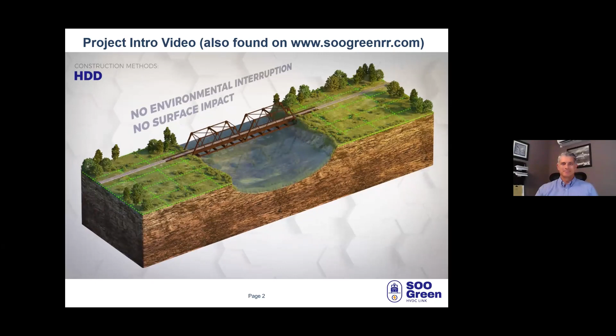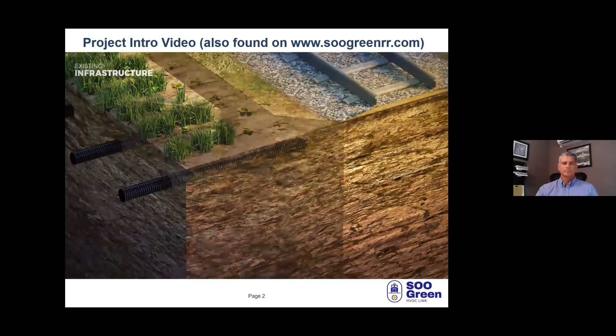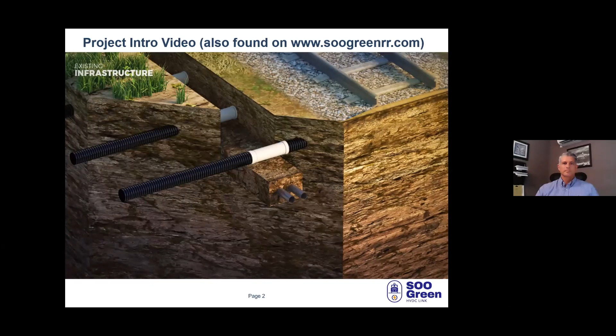When intersecting existing drain tile, smaller tiles will be cut and capped to allow the trench to be dug and the conduits installed. Once conduits are in place, the tiles will be repaired and the trench filled with existing native soil. Depending on current use and flow rate of drain tile, conduits may be placed under larger tiles without cutting.